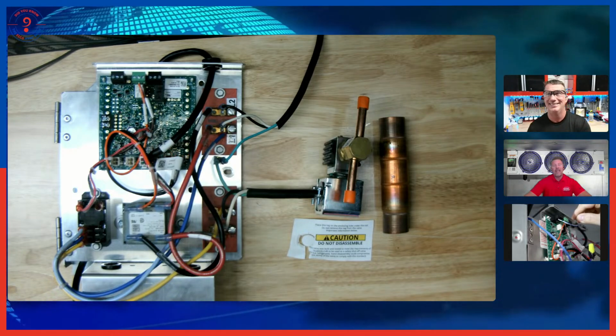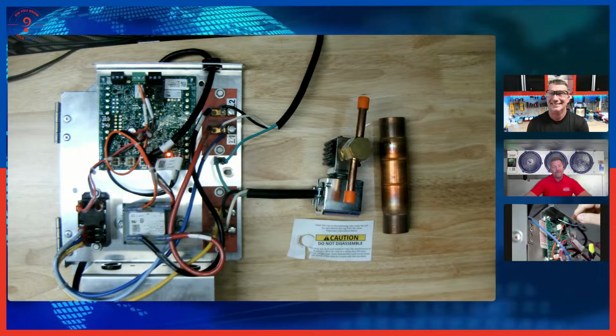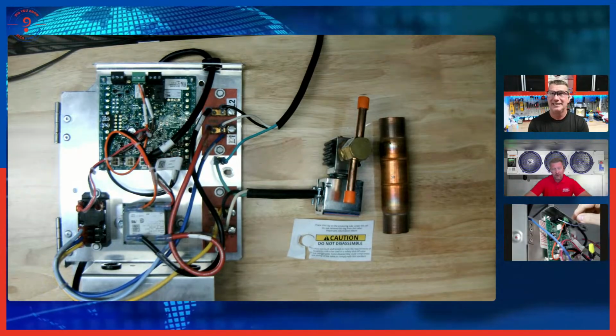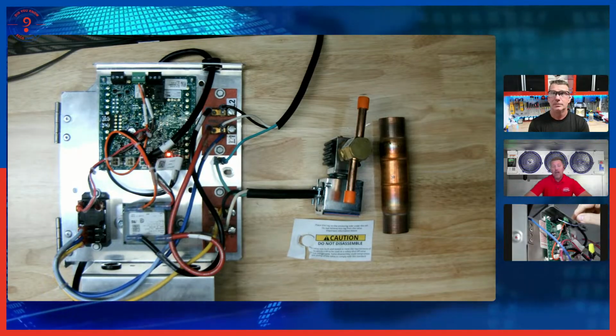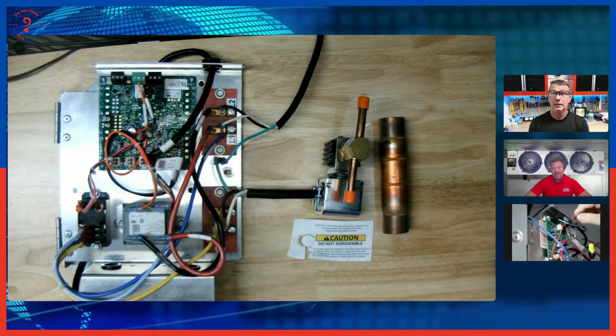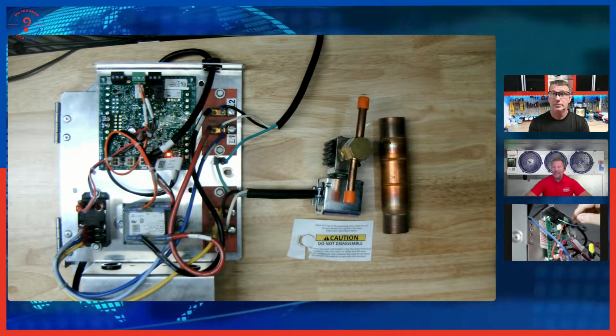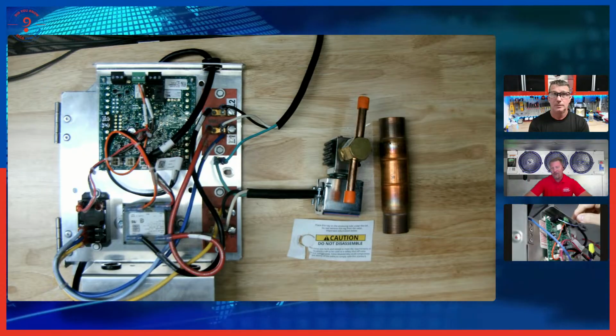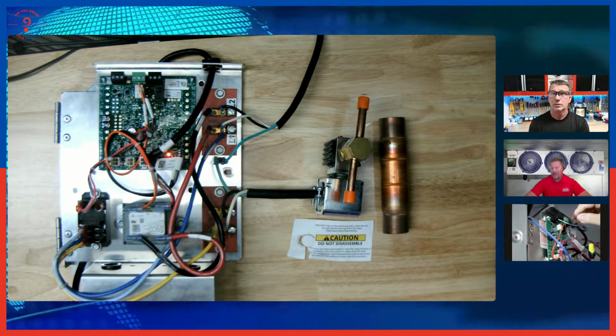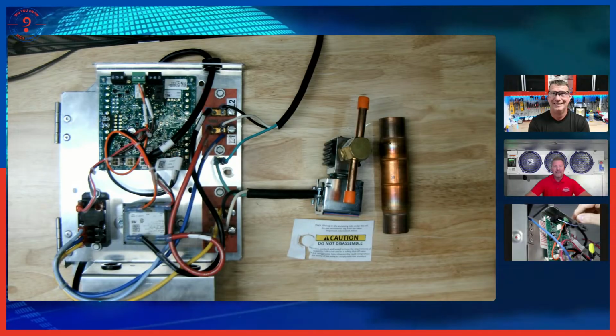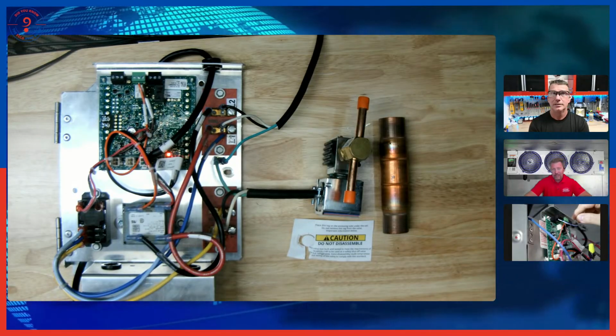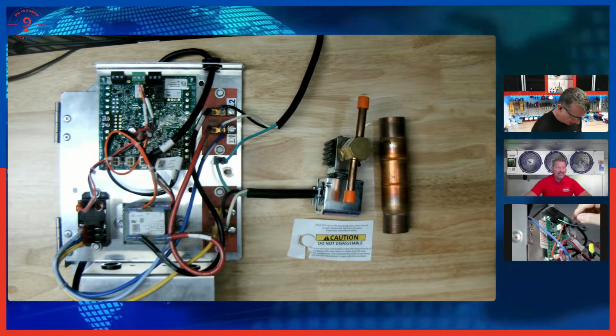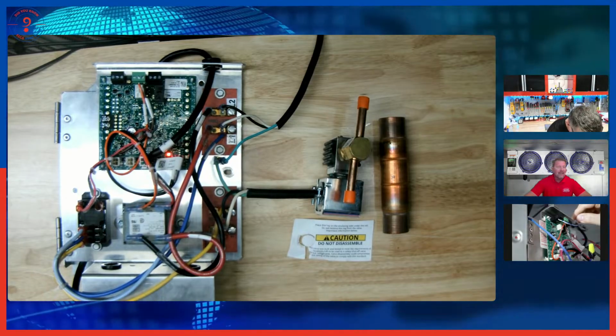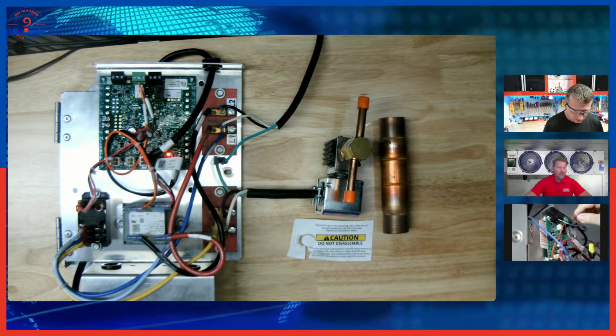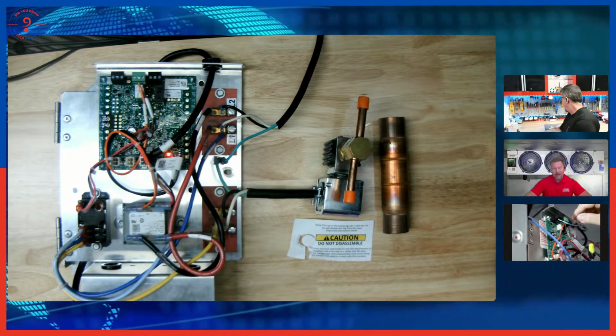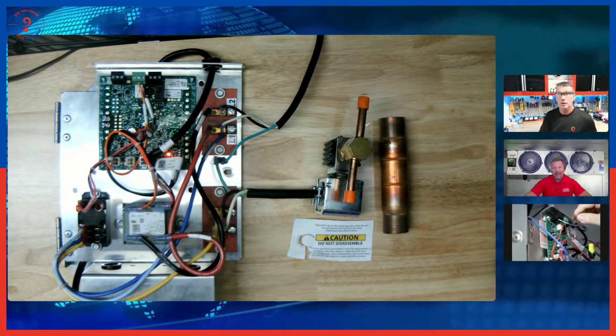Oh, you know what? If you did set it off, another important safety note on our RDS kit: it will not reset itself. It doesn't matter how many times you shut the power off, how many times you tap the sensor or hit it with a wrench or whatever, as we techs have done in the past. The only way to reset it is to press the micro switch on it. That is another safety we've built in to prevent the client from going in and just turning the breaker off and on, and lo and behold, they're back up and running.